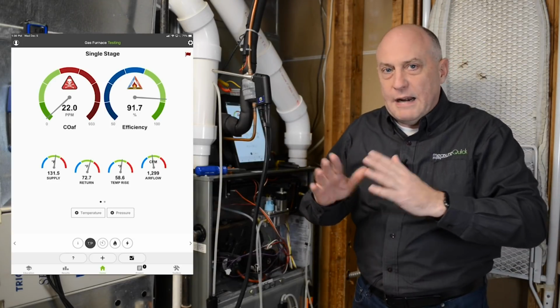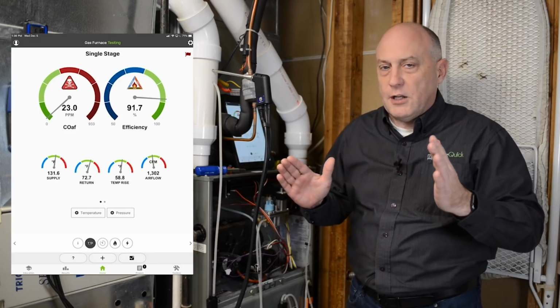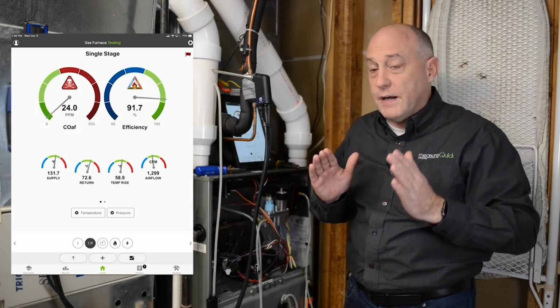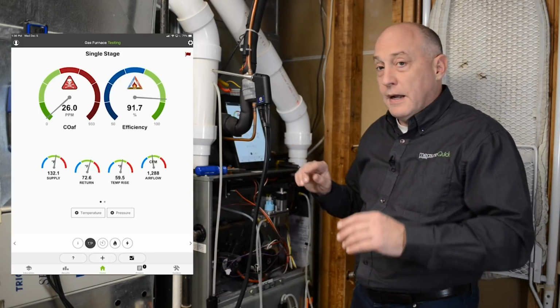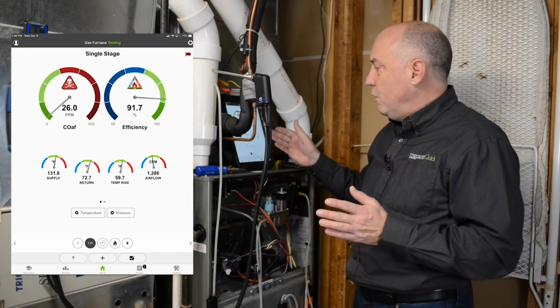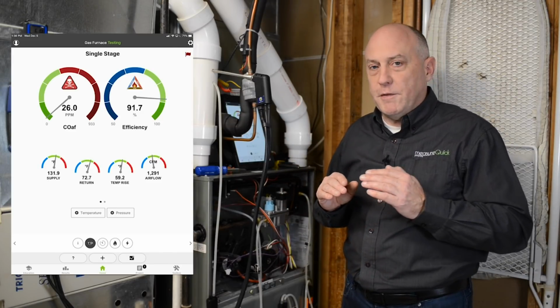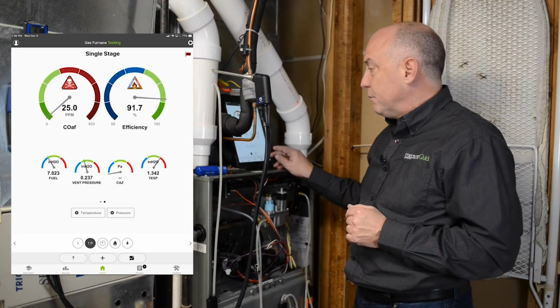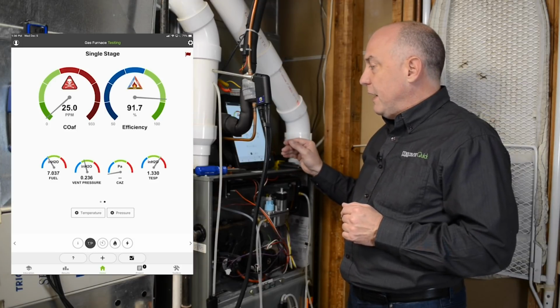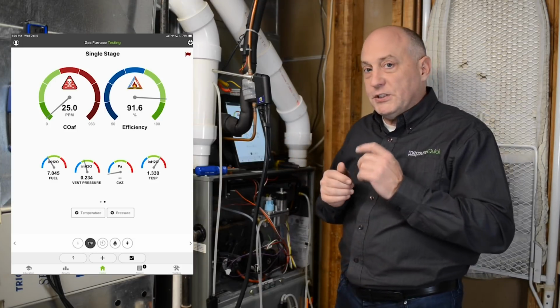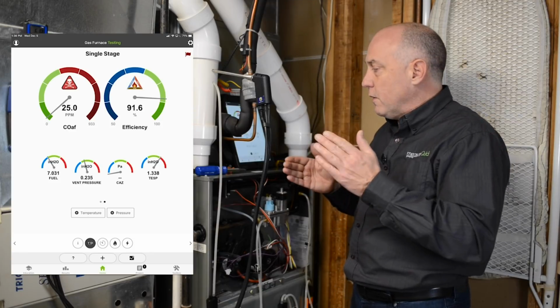So you can see how I can get everything at once and I'm not running around taking all these different measurements. So this is very, very quick as we're doing this. Automatic calculation of my airflow. So I'm moving 1,295 CFM of airflow across here, again, in the acceptable range. Fuel pressure is at about 7 inches of water column. Remember, 6 inches is our cutoff on there, so it's okay still.